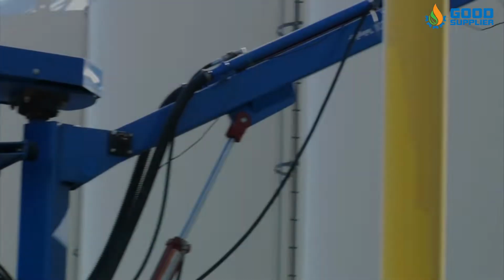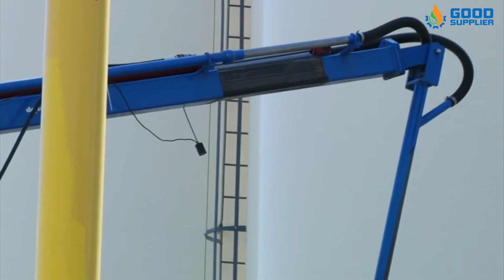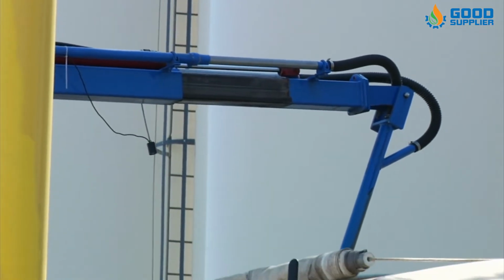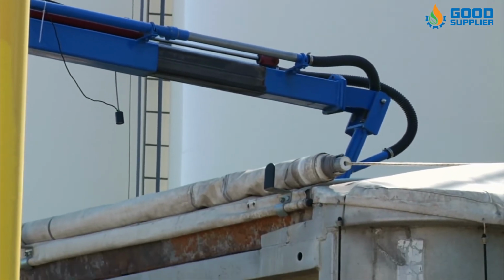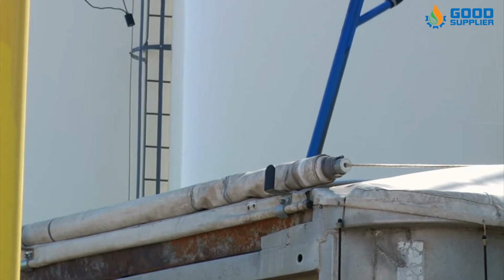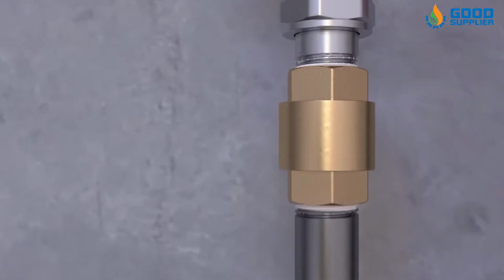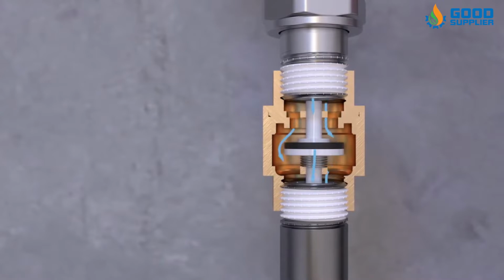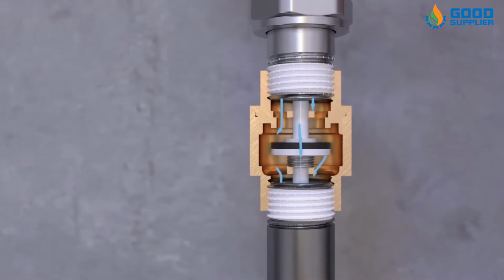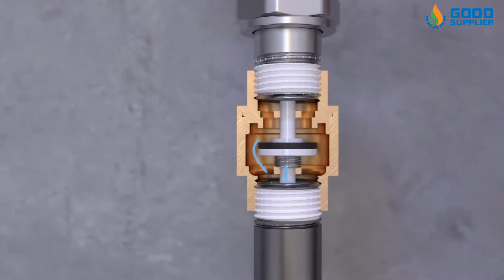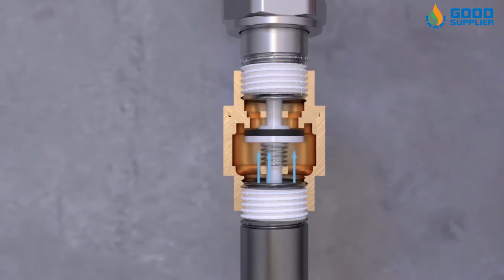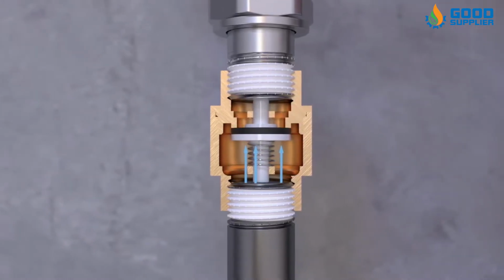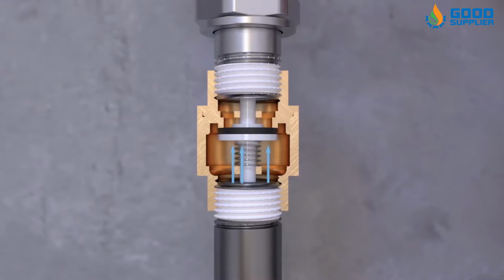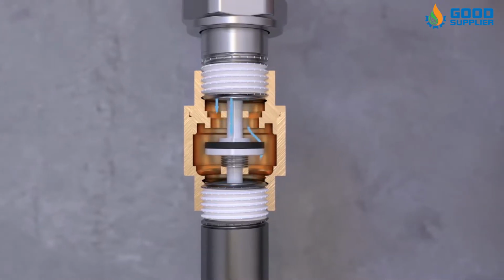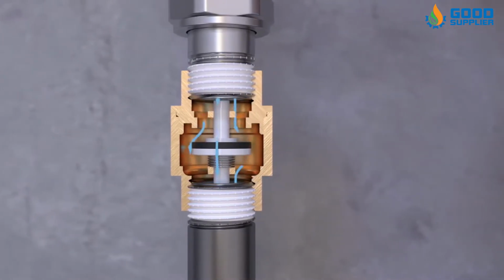They will both operate in combination with the motor, cylinders, and hydraulic pump. The valve controls the flow of fluid for the correct operation of equipment. Check valves are used in many different applications. For example, they are often placed on the outlet side of a pump to protect the pump from backflow.